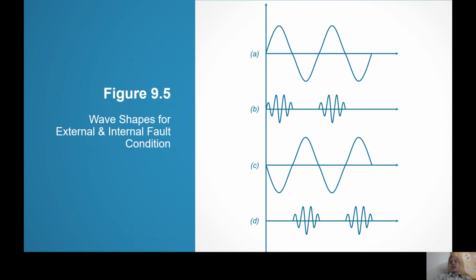And when it is transmitted like this, for half the cycle the carrier signal is not available. So because the carrier signal is not there, tripping is allowed. It is a blocking scheme. There is no carrier signal, therefore the breakers at A and B will trip simultaneously and will reclose simultaneously. Our purpose is served.